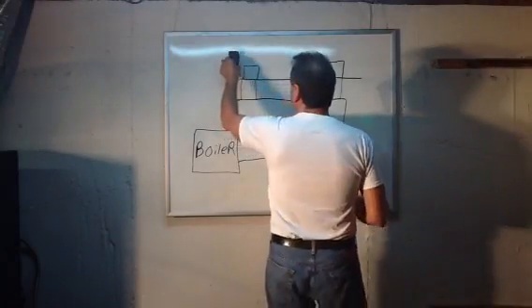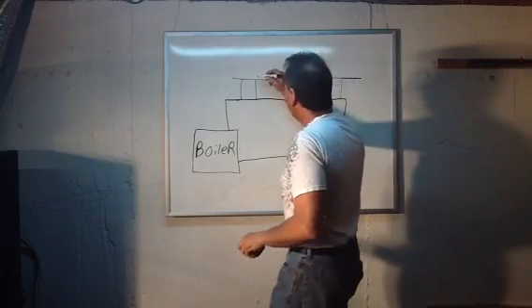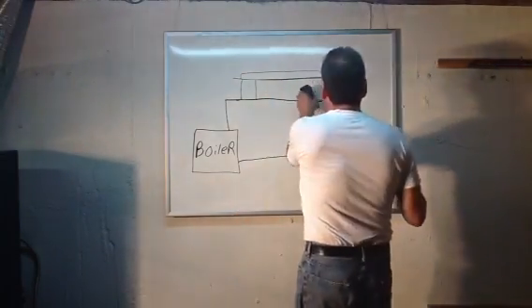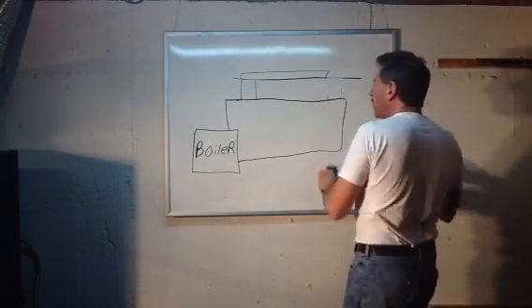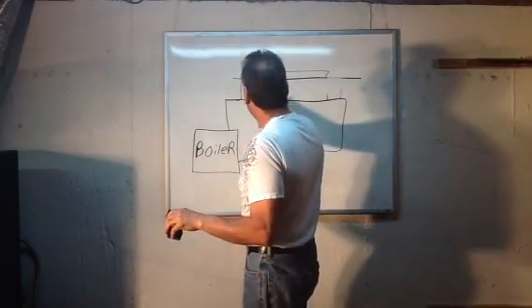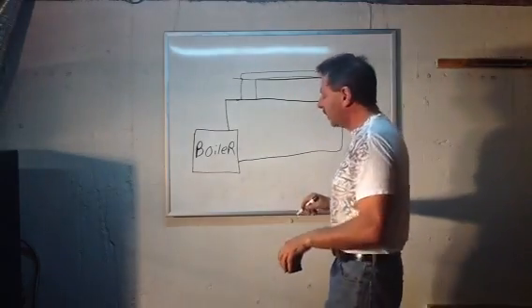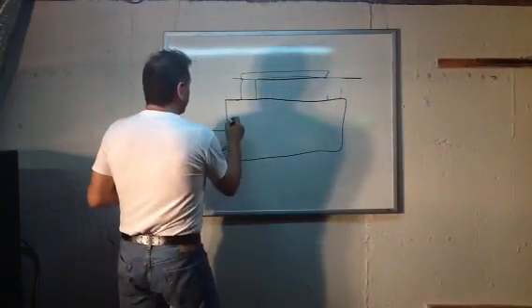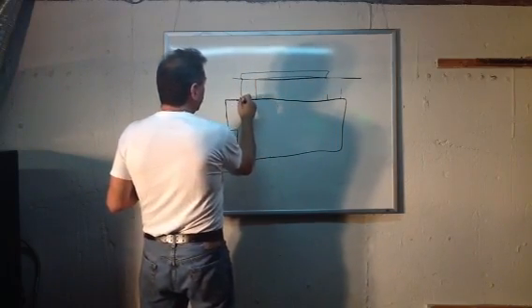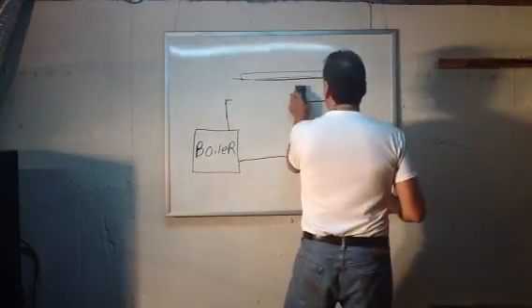It didn't take 100% of the water and that worked fine with convectors. But when people want to upgrade and get rid of those ugly radiators, somebody comes in, probably was cheap and didn't know what they were doing, and put baseboard in. Now the baseboard, since the half-inch copper is sticking up for the convector and they thought that would work, they would just take the half-inch copper and tie it to the baseboard, either inside the baseboard or move it over.